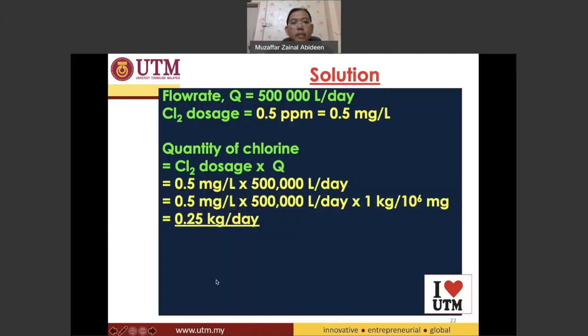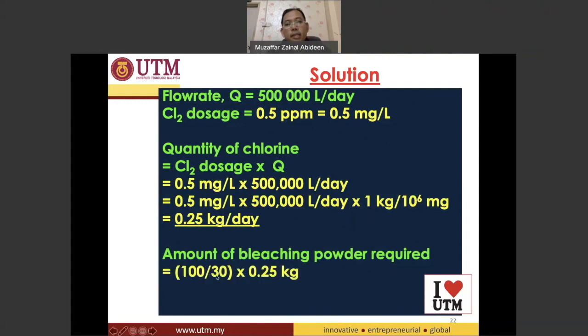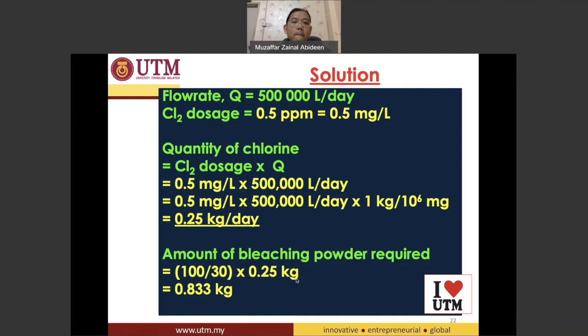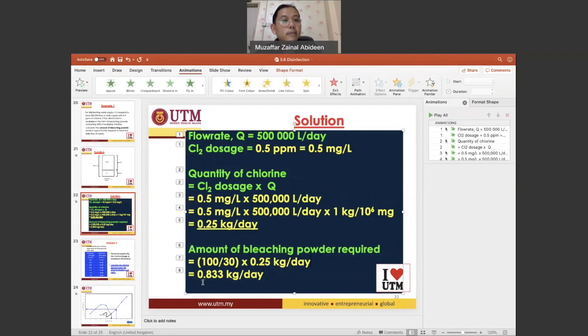The quantity of bleaching powder required is found using a ratio: (100 ÷ 30) × 0.25 kilograms. The bleaching powder needed is 0.833 kilograms per day. So the answer to the question — the amount of bleaching powder required to treat the daily flow of water — is 0.833 kilograms per day.